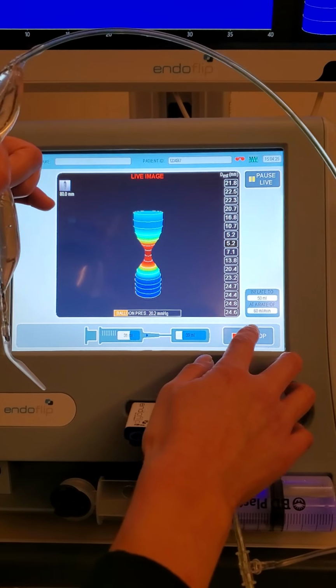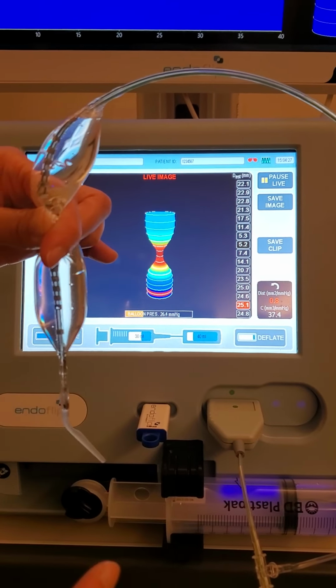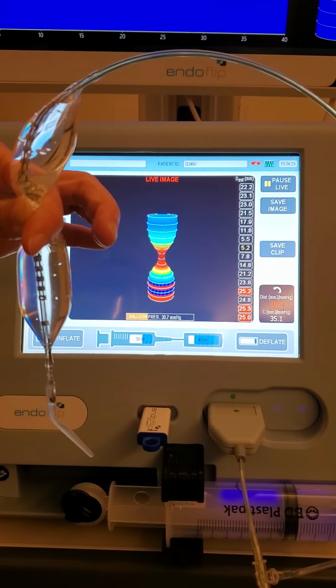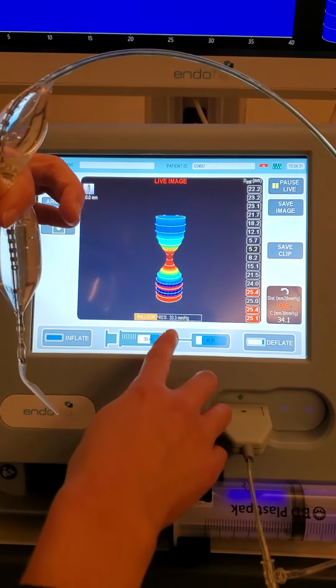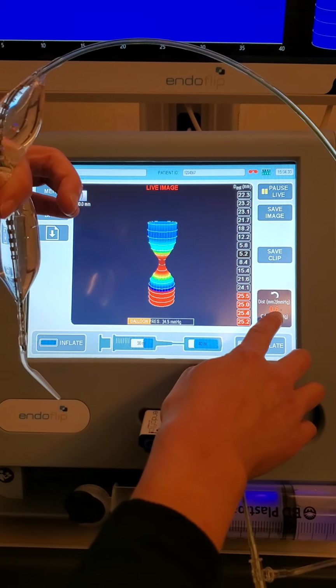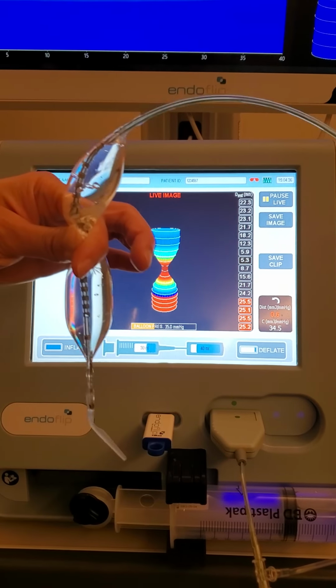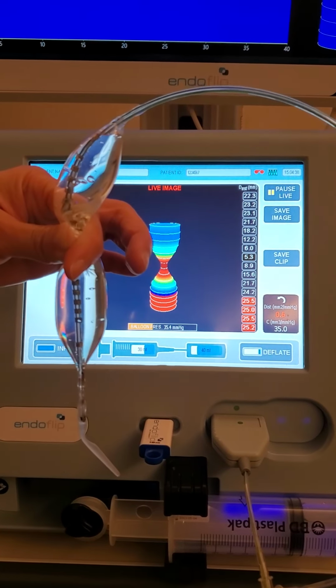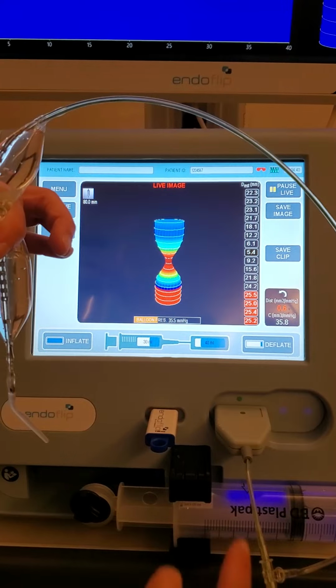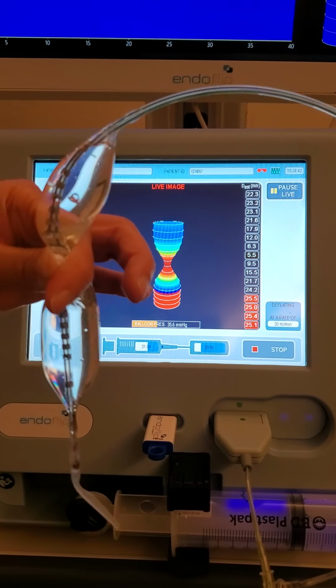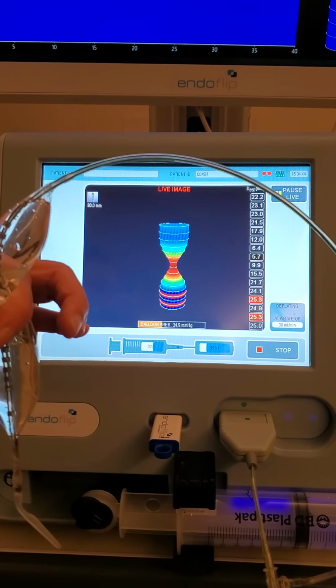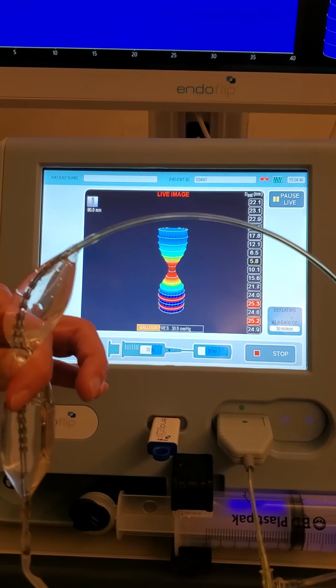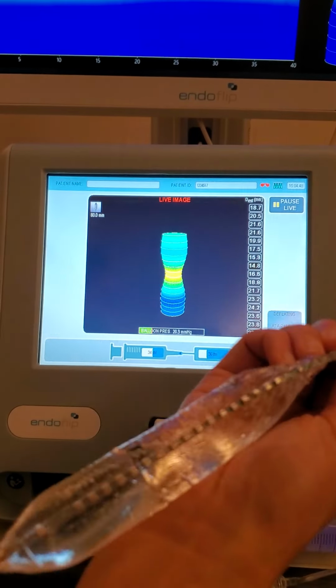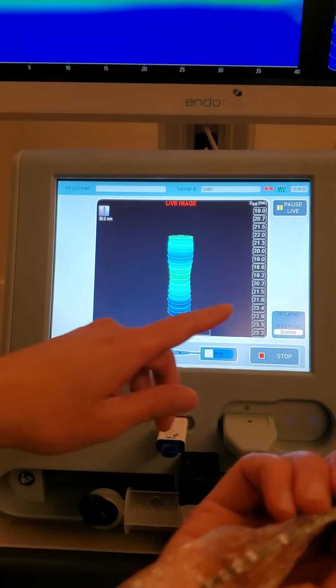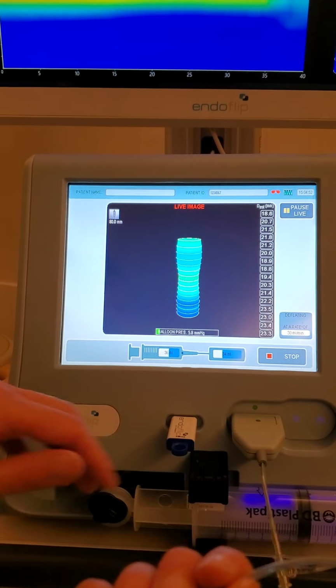At each point, you would stop whenever the physician says that's the balloon volume that I want. Again, they'll read off the balloon pressure, distensibility, and diameter, and so forth, and you'll write that down onto the worksheet. When you're finished with the procedure, you just click deflate. You will just let it continue to deflate on its own. Sometimes the physician will pull it out of the patient before it's all the way done deflating, but continue to let the machine deflate even if it's out of the patient.